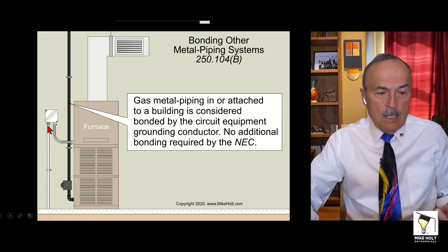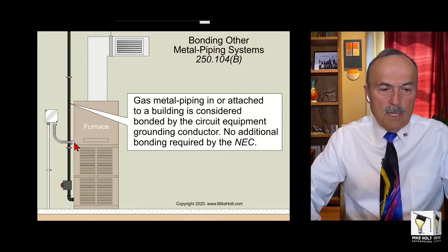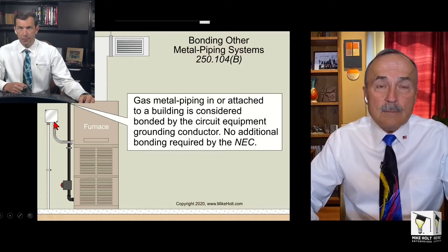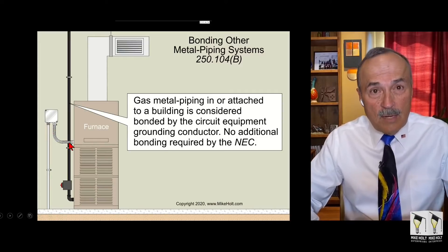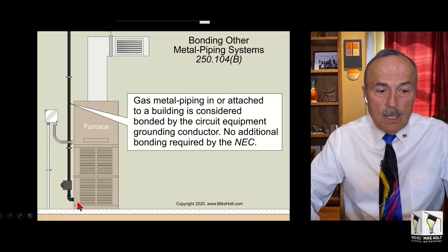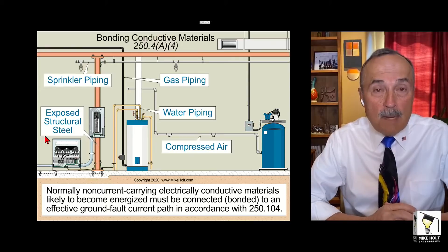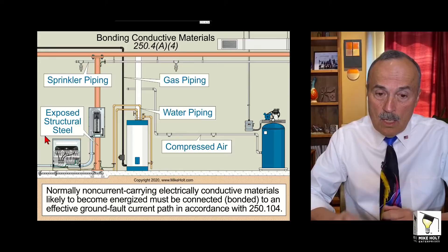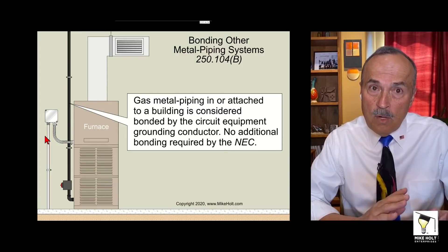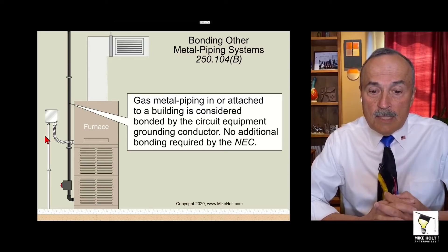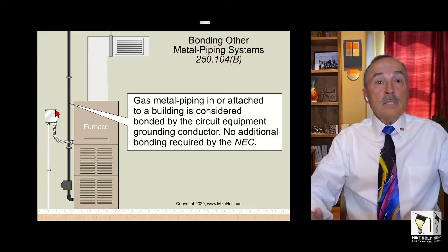EMT is considered an equipment grounding conductor. In this case, probably a 15-amp circuit, not more than six feet of flex metal conduit, which is considered part of the effective ground-fault current path. That means the furnace and the gas piping connected to it are already connected to the equipment grounding conductor — they're bonded. Per 250.104(B), no additional bonding is required by the NEC. You're done.